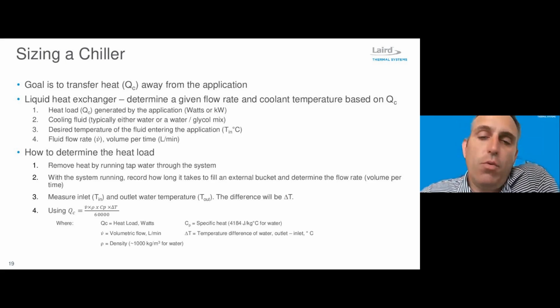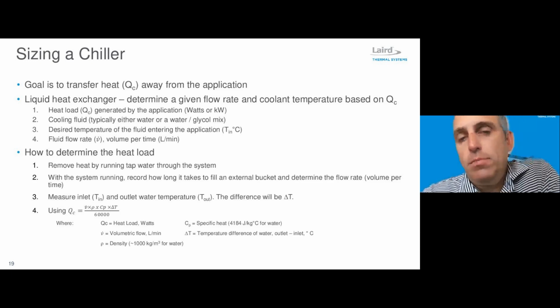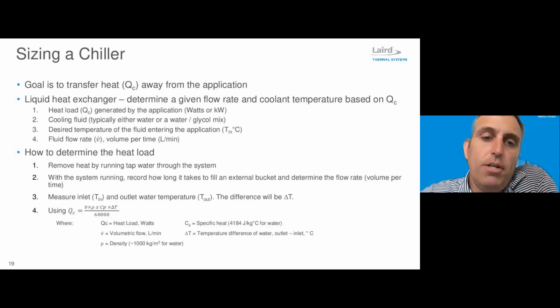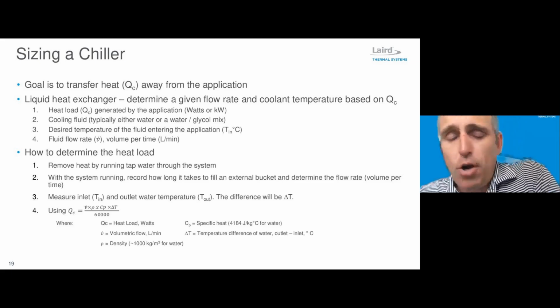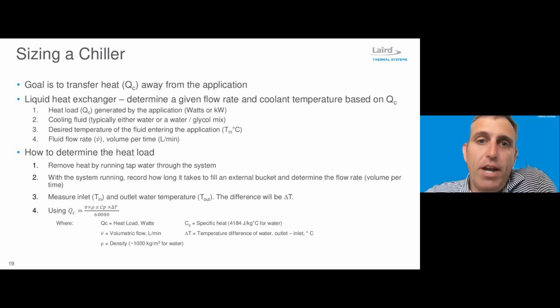And so that's exactly what we need to know in order to size our chiller. We need to know how much heat's being put into the fluid. We need to know what type of fluid it is, because there are different thermal properties that impact the performance of the system. We need to know at what temperature that fluid needs to be and how much of it they need. What is the flow rate? And so oftentimes this information is provided by the manufacturers of the equipment, but sometimes it's not.